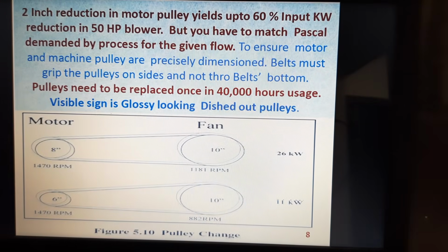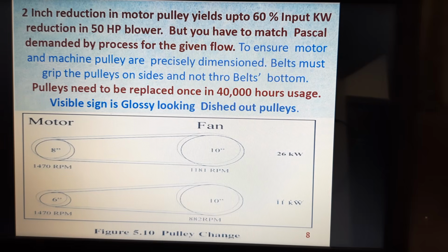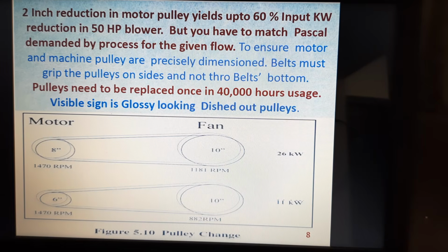Overall, if you see a 2-inch reduction in motor pulley: an 8-inch motor pulley was driving a 10-inch fan pulley at 1470 RPM motor speed, and the fan RPM was around 1180 RPM. It was taking almost 26 kilowatts on a 50 HP blower motor. When the motor pulley was resized from 8-inch to 6-inch, the 1470 RPM motor drove the blower at 880 RPM only, and the drop in power is almost 11 kilowatts. This is to reinstate the fan affinity gain, and belts and pulleys play a critical part in reducing the power lost in transmission from the motor to the blower.